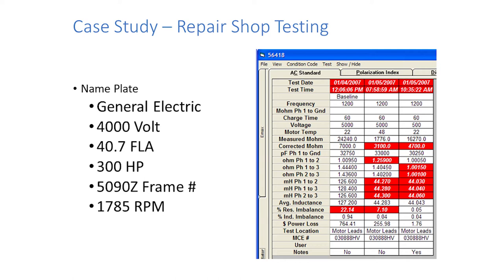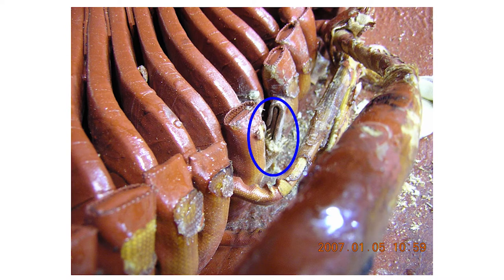It's nice to have these standards and limits you're going to accept motors at. Shops have the same limits for motors they're rewinding. They decided to take this motor apart and take a look. Where they're putting coils together — they're supposed to be soldered, but it just didn't get done. It was probably a Friday or a Monday. A simple quality control test was able to identify a stator-related anomaly. This motor would start arcing immediately. A lot of reliability testing is just identifying conditions conducive to failure and getting rid of those conditions — so the motor lasts as long as it's supposed to.